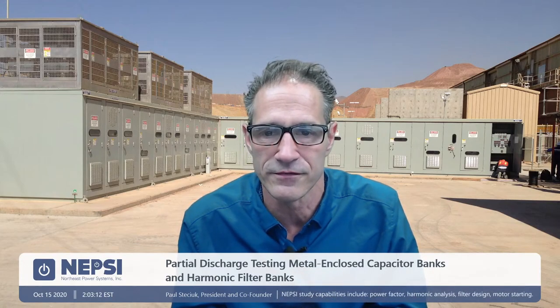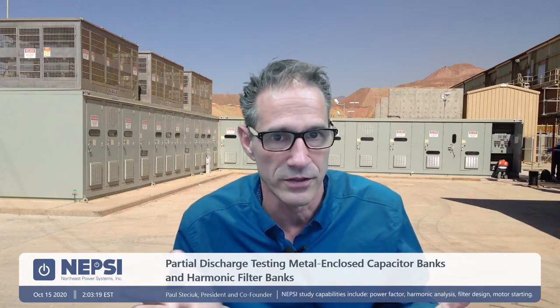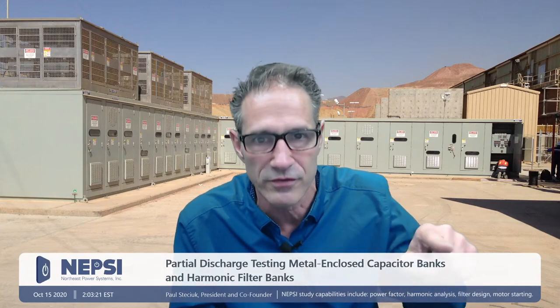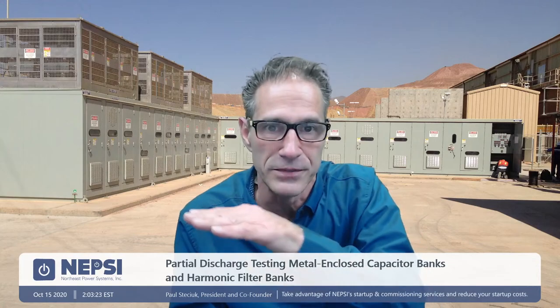We have talked about SFRA testing a few weeks ago in a Tech Talk, and that was a test that we conduct at the factory during factory acceptance testing to determine the filter characteristics and to confirm the operational characteristics of the filter, to make sure we got in fact the impedance waveform or impedance profile for that filter that we would hope for.